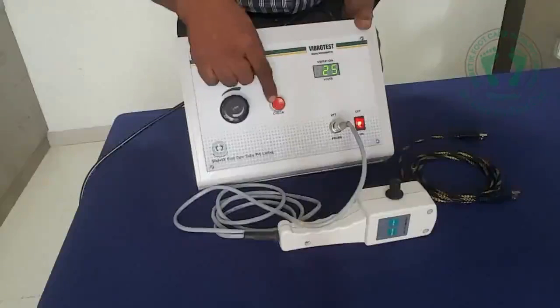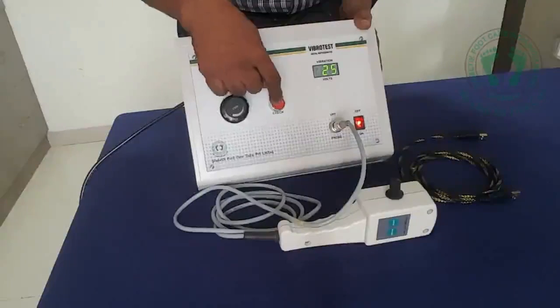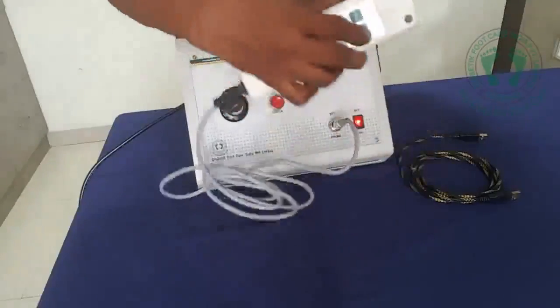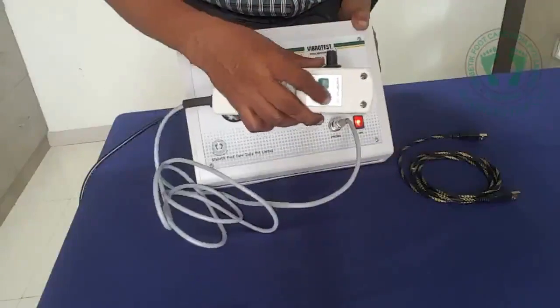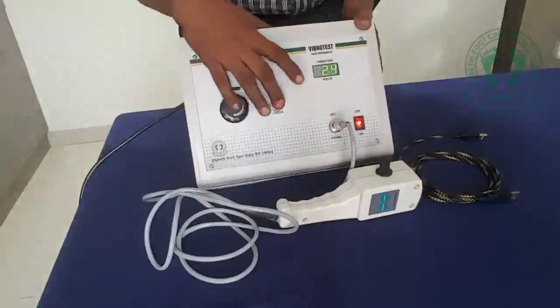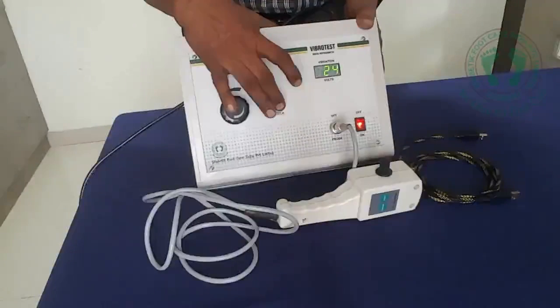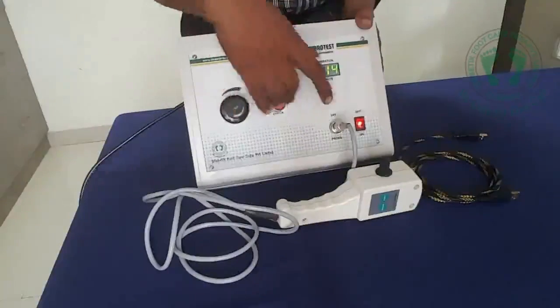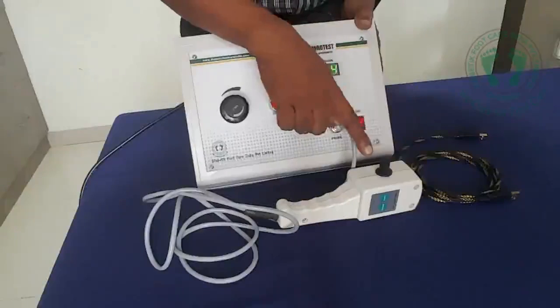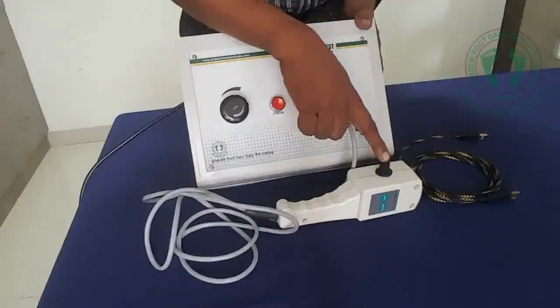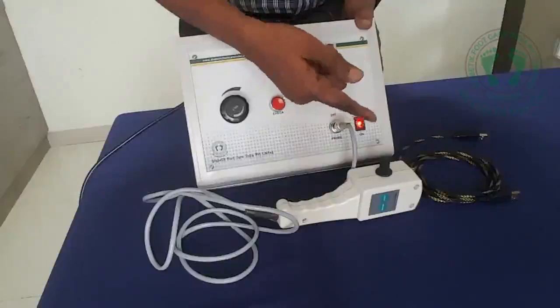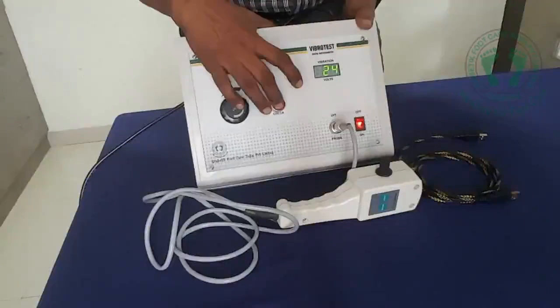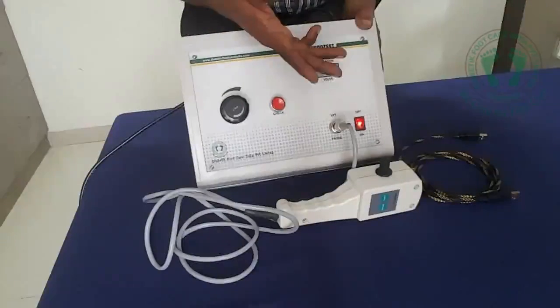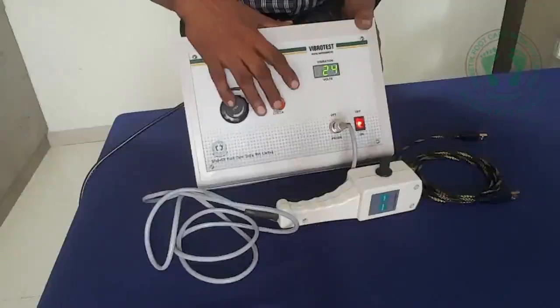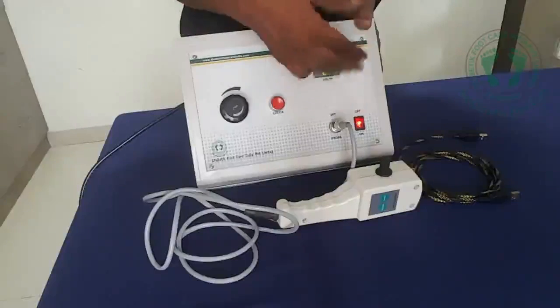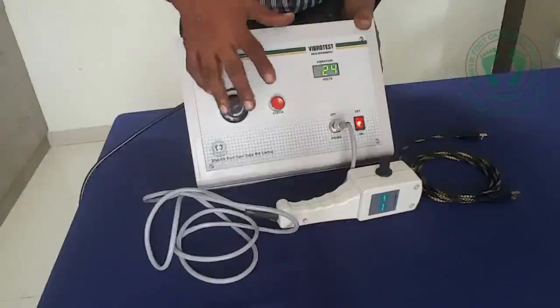Here there is a check key, and on the probe also there is a check and record key. The check basically stops the vibration. When I press this, the vibration to the probe stops. So when the patient feels the vibration and I press it, the vibration stops, and he has to say yes or no if he's not getting it. When I release it, he should say he's getting it, meaning the value is correct.